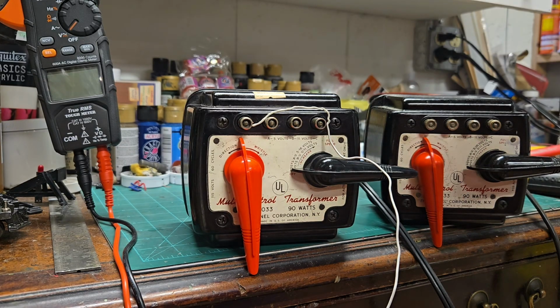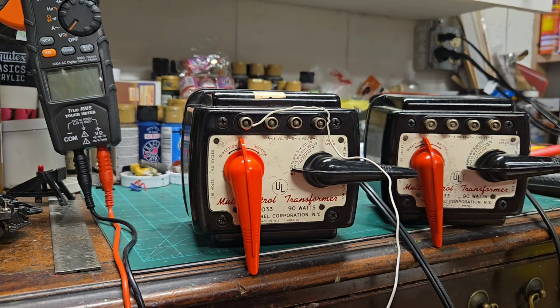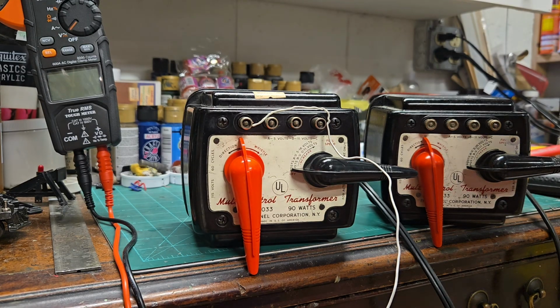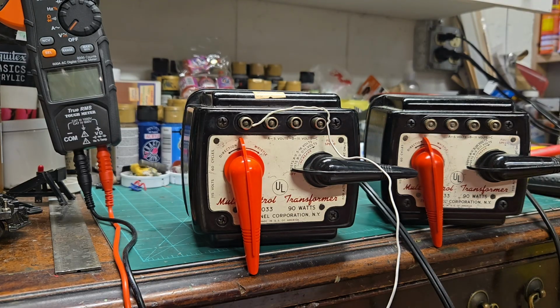Knowing that, you probably want to provide transient voltage surge protection if the manufacturer hasn't provided it in their equipment. Even if they have, I would question just how good that transient voltage surge protection is. Typically, transient voltage surge suppressors for solid state electronic equipment tend to be the most expensive surge protectors out there that you can buy. In other words, a lightning arrestor won't do it; it really needs to be something for transient voltage surges.